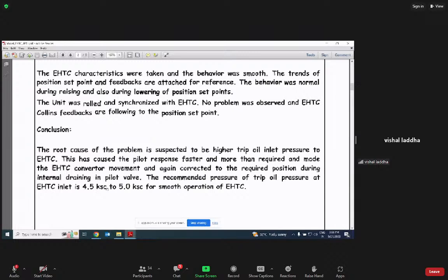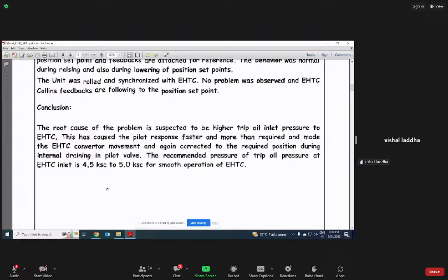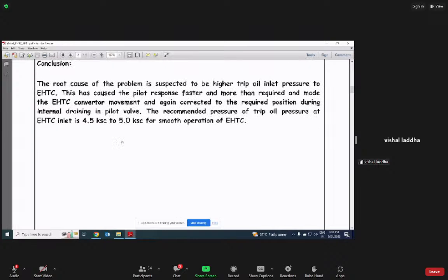The recommended trip pressure at the EHTC inlet is 4.5 to 5 for smooth operation of the EHTC. It is at the inlet of the EHTC. This is not the trip header pressure. This is the inlet pressure; the correction point is also given just below the EHTC points where the auxiliary follow-up piston is present. So this is my first case study.